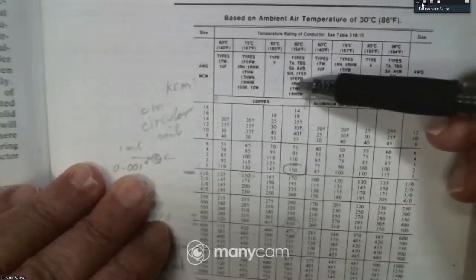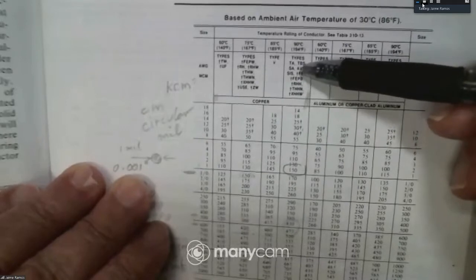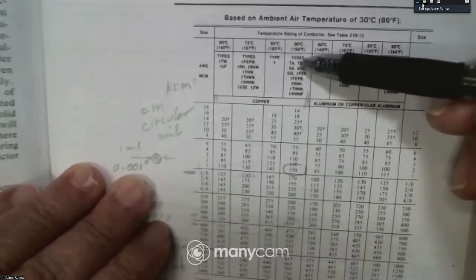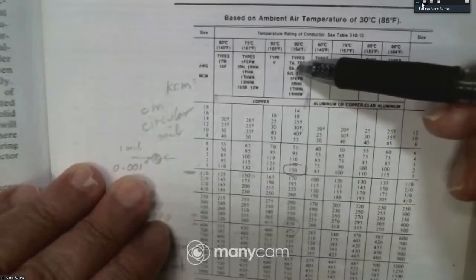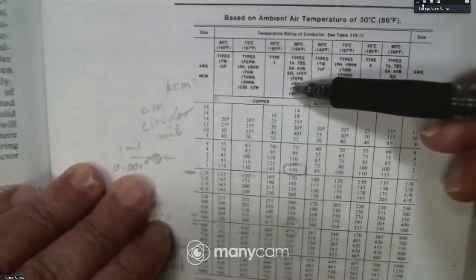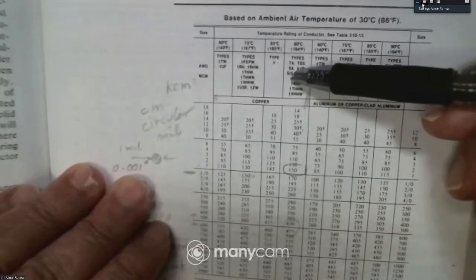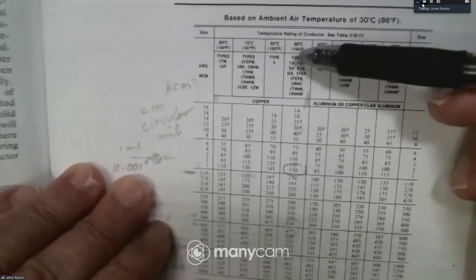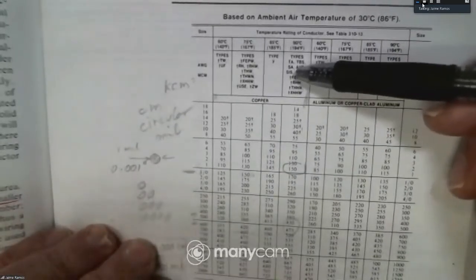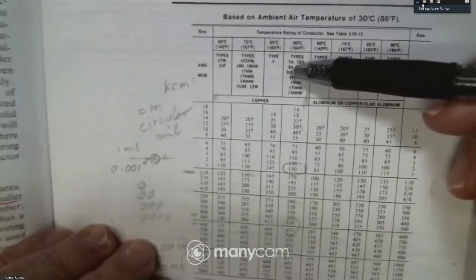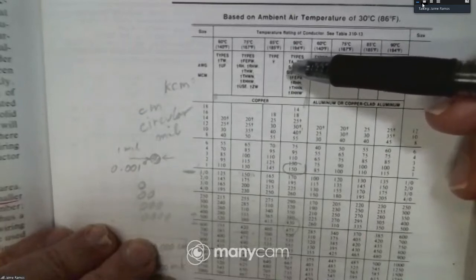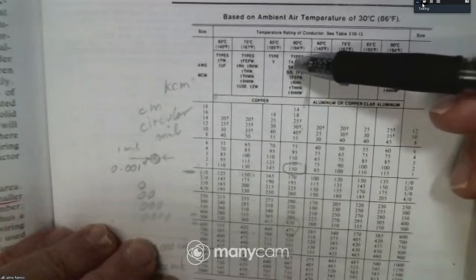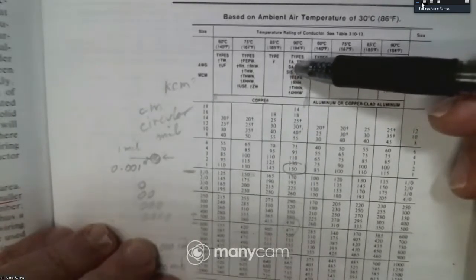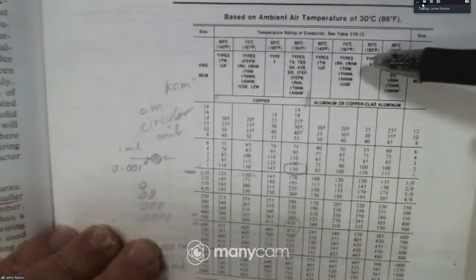So all these acronyms are for the material of the insulation. And then that material of the insulation is rated for 90 degrees. So no more than 90 degrees on these insulations, because more temperature degrades the insulation, and eventually there'll be a failure in the insulation of the cable.